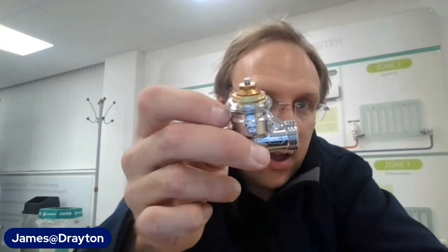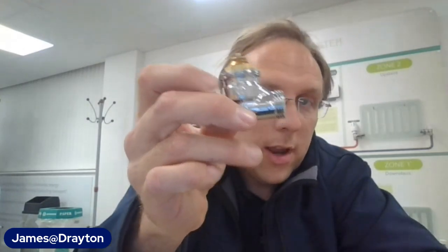That means as the demand decreases, the pump speed will decrease, and you could get to a scenario where if you've got this set to say 50 litres an hour, you might not be getting that through your pump. So it appears that your system would then go out of balance. That is sort of true in so much as you won't be getting consistent flow rate into each radiator as per your setting, because there is just not enough flow there. But by that time, the system will have modulated down, and so it's unlikely to harm your efficiency too much.